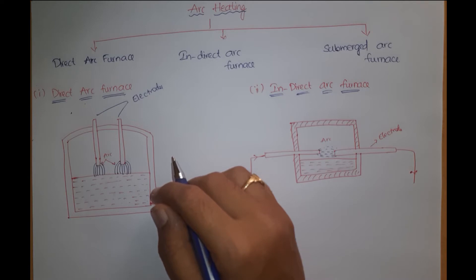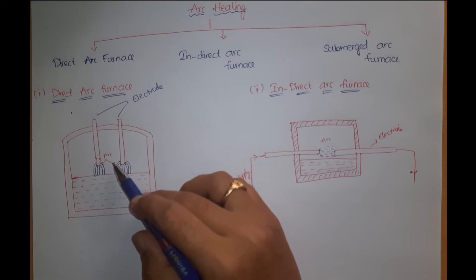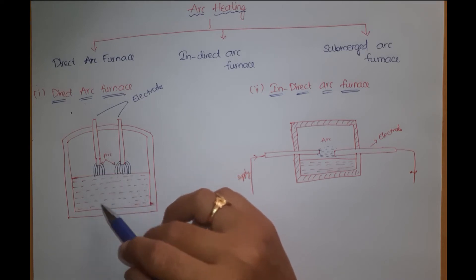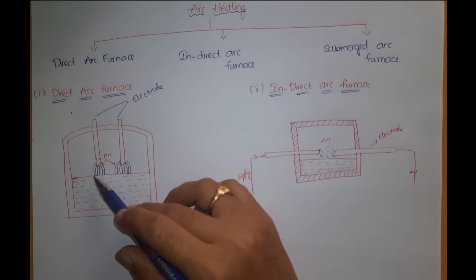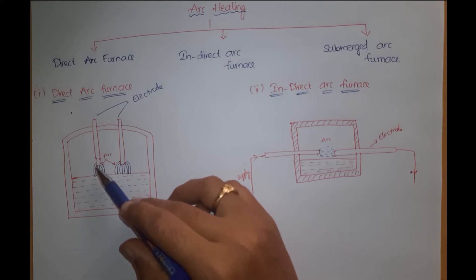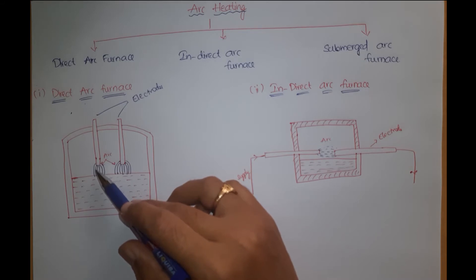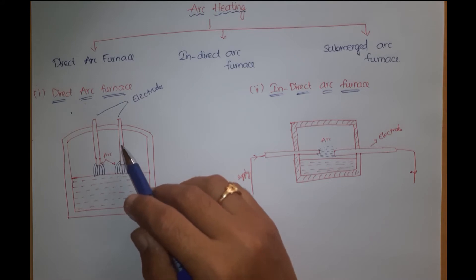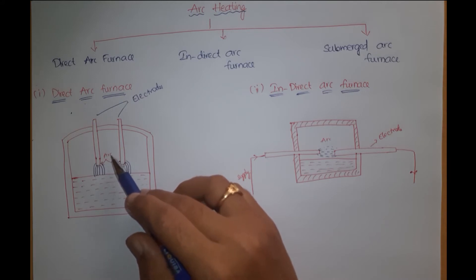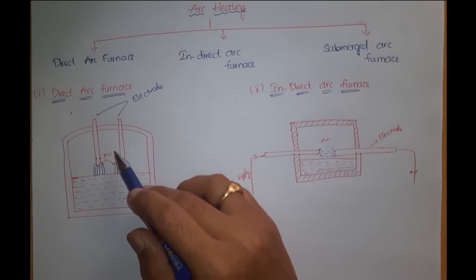When you apply certain high voltage across the air gap between the electrodes and the charge to be heated, the air in the gap gets ionized because of the influence of electrostatic forces, and this gap becomes a conducting medium. So when this current flows in the form of continuous spark, that is called an arc. When electrodes are made up of carbon or graphite, the temperature obtained can be in the range of nearly 3000 to 3500 degrees centigrade.